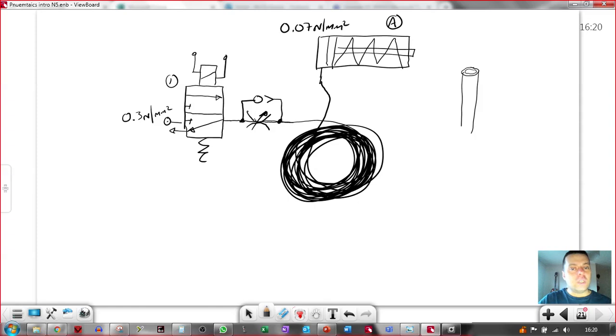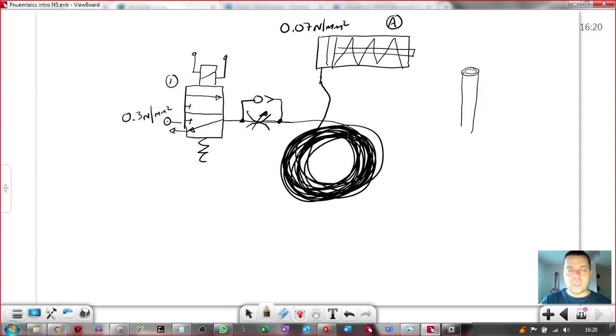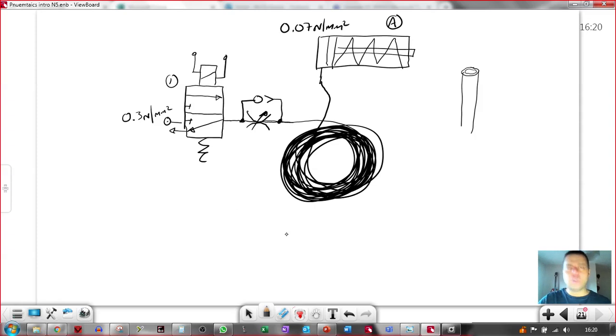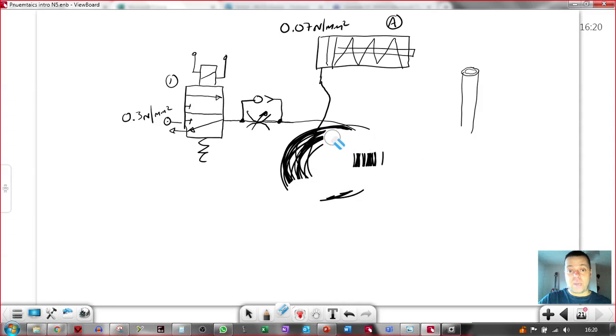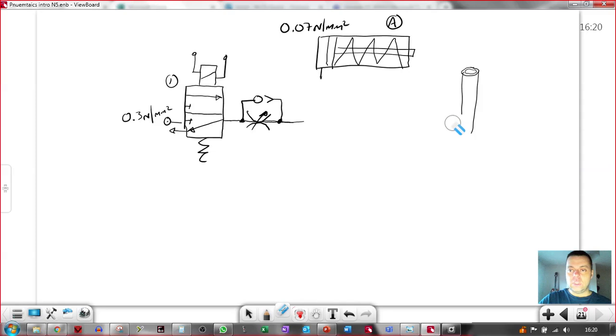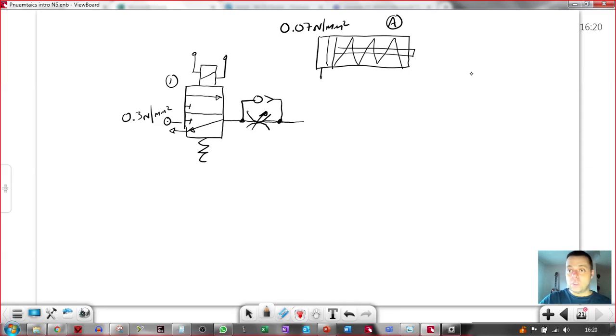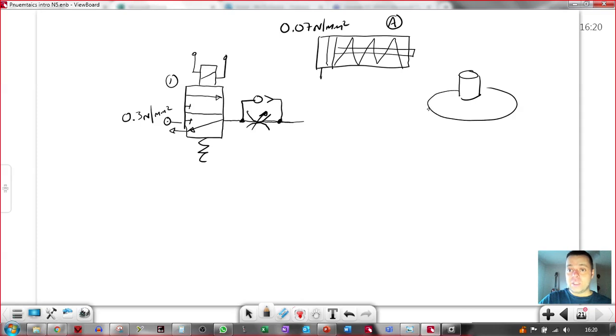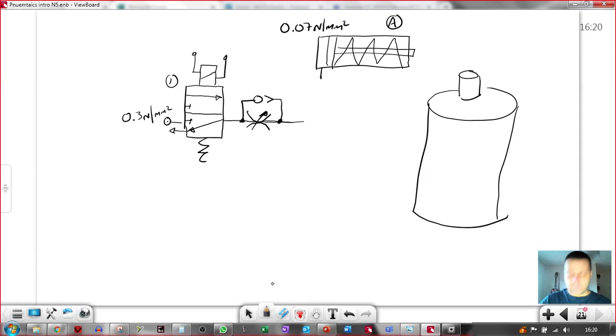That reduced flow rate is going to have a much harder job of increasing that massive volume up to pressure. And that's essentially what we do, but we don't use reels of hoses. We use a new device, and it's like a passive device, a dumb device. It's called a reservoir. And all it is, is a big empty tank. It's got a port connection on the top, and it's just a big bottle, big metal bottle. Big empty void inside there.